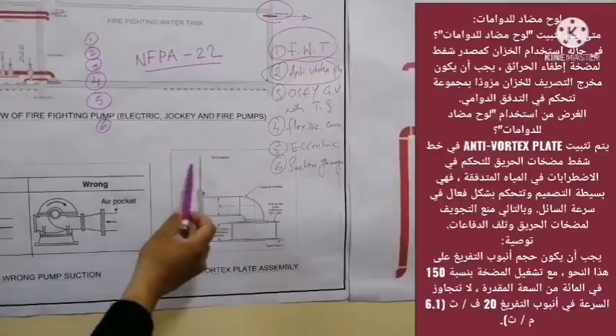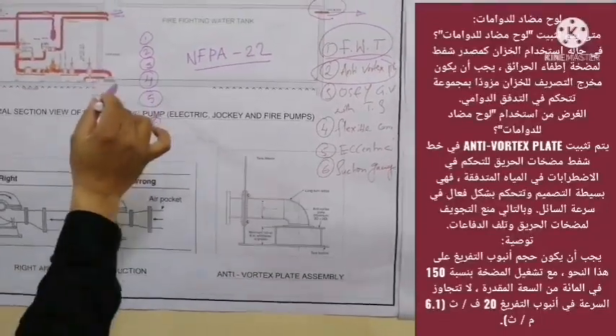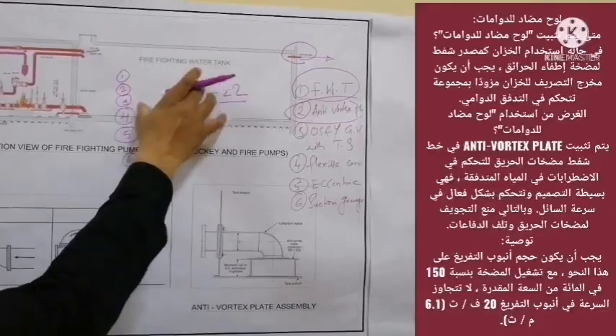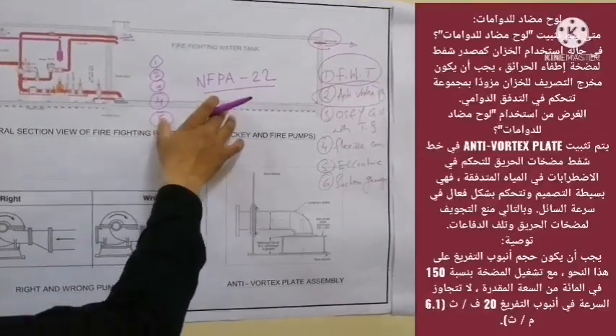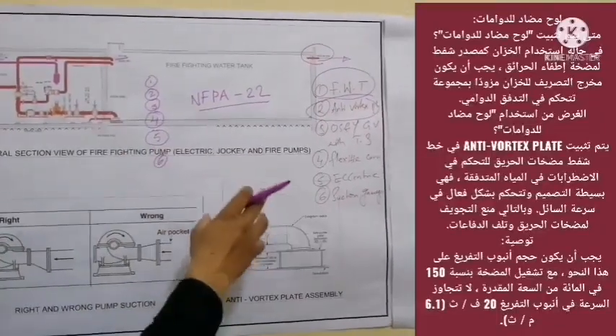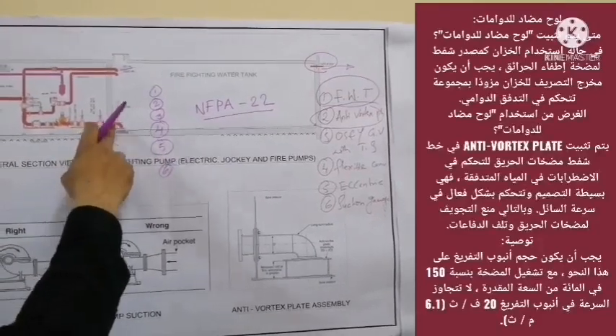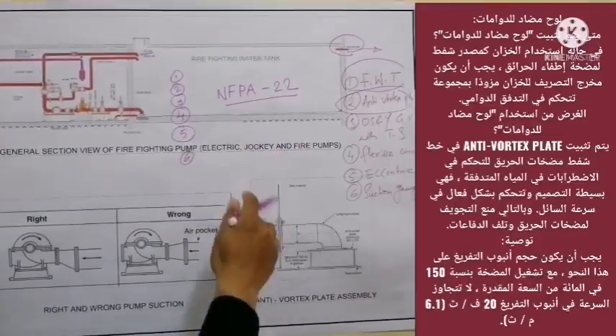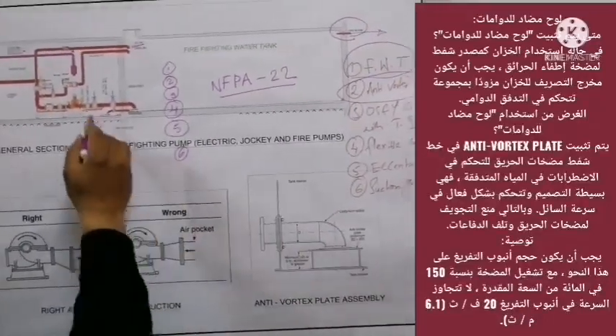Let's come to number two — the anti-vortex plate. This is the anti-vortex plate assembly, which is installed inside the water tank. The anti-vortex plate is installed at the discharge outlet where a tank is used as a suction source for a fire pump. The discharge outlet of the tank shall be equipped with an assembly that controls vortex flow. It is installed in the suction line of the fire pump to control turbulence in flowing water. They are simple in design and very efficient at controlling the velocity of fluid, thus preventing cavitation to the fire pump and damage to pump impellers.